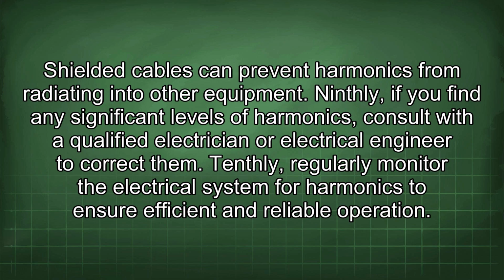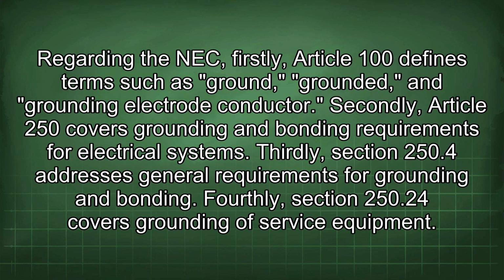Ninthly, if you find any significant levels of harmonics, consult with a qualified electrician or electrical engineer to correct them. Tenthly, regularly monitor the electrical system for harmonics to ensure efficient and reliable operation. Regarding the NEC, firstly, Article 100 defines terms such as ground, grounded, and grounding electrode conductor. Secondly, Article 250 covers grounding and bonding requirements for electrical systems.